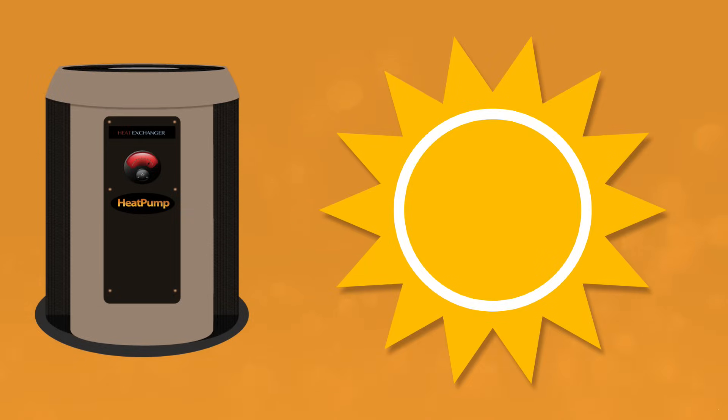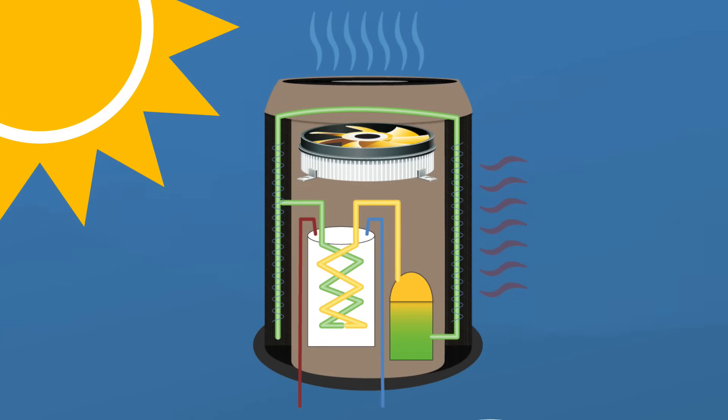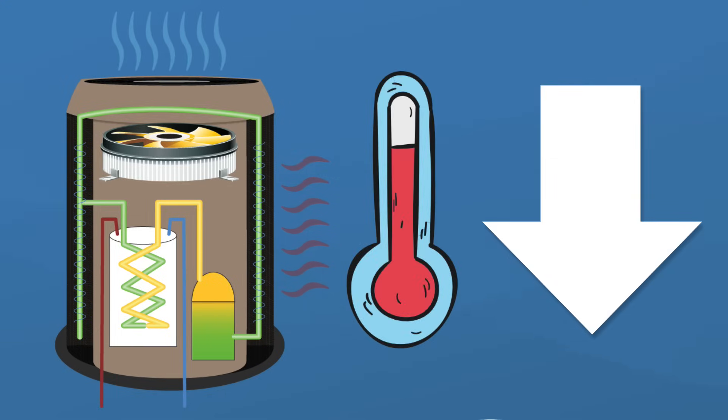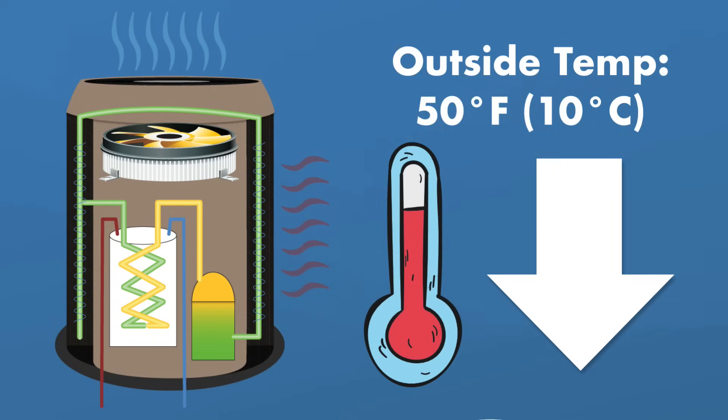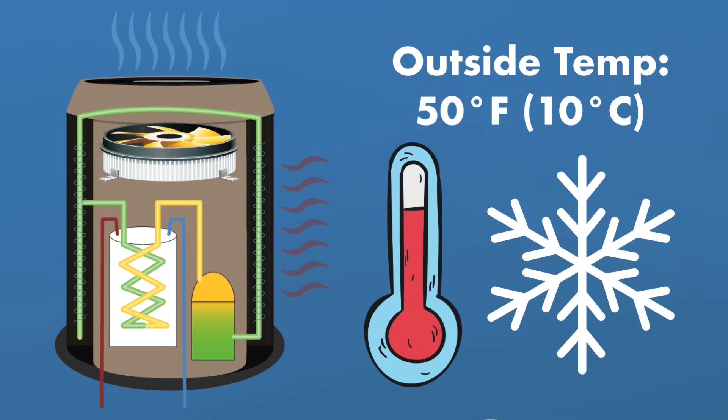It also matters what climate you live in. Your pool heat pump uses ambient temperature to heat your pool water. And that means the warmer the air is outside, the more heat the pump's evaporator can absorb, and the more efficiently it will run. Once temperatures start to drop, the heat pump becomes less and less effective. The ambient temperature needs to be at least 50 degrees Fahrenheit or 10 degrees Celsius for the unit to properly work. So if you experience consistent colder temperatures throughout the winter, a pool heat pump may not be worth it.